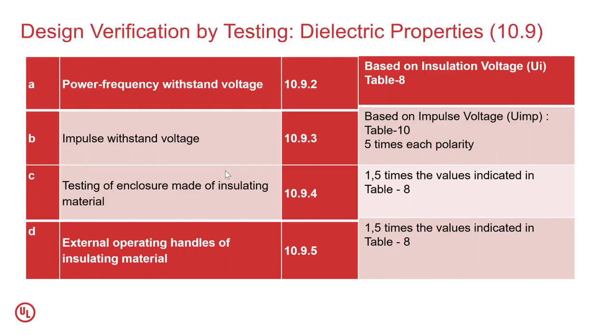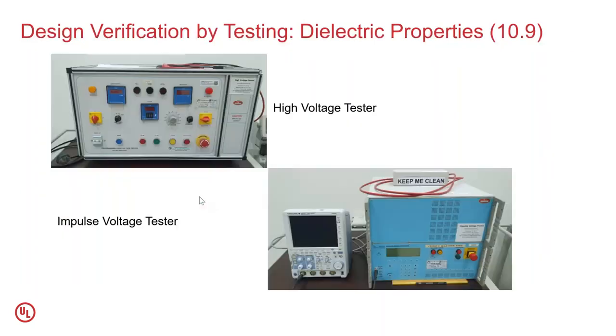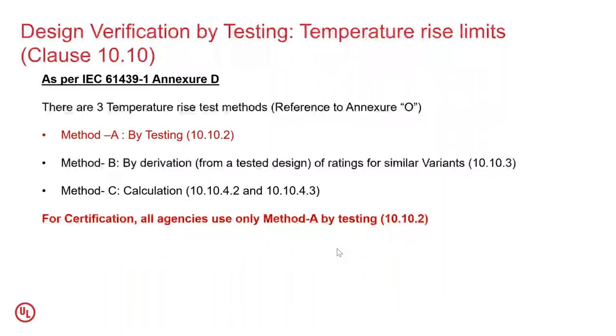So these four tests are very, very important under dielectric properties under 10.9. Normally you see this is a high voltage tester and this is an impulse voltage tester.